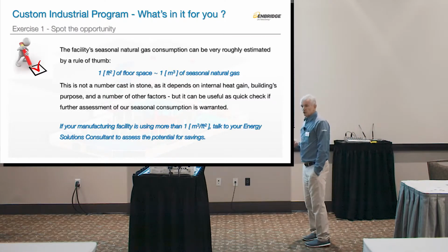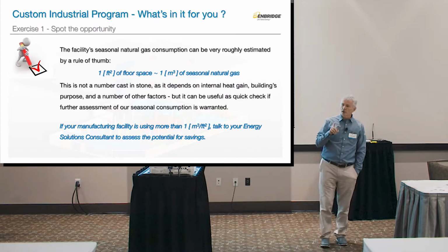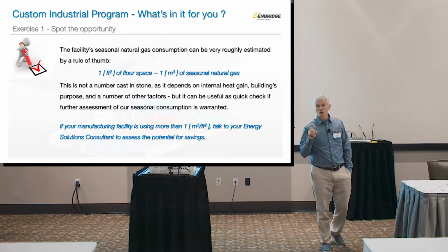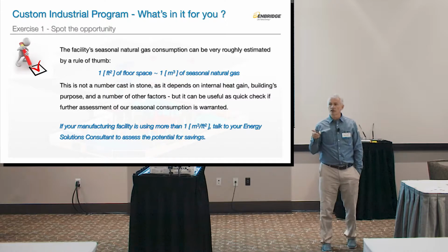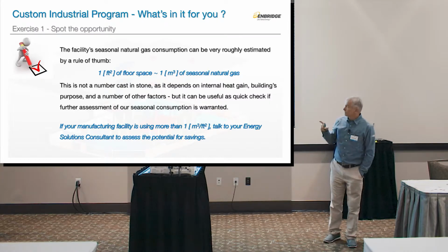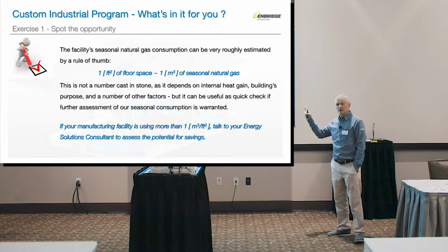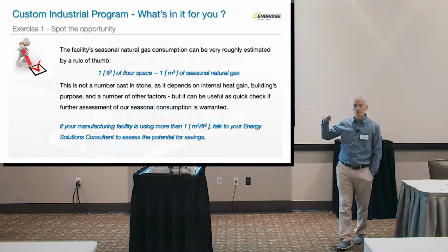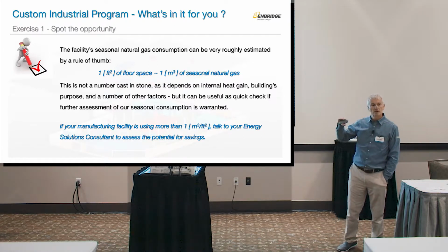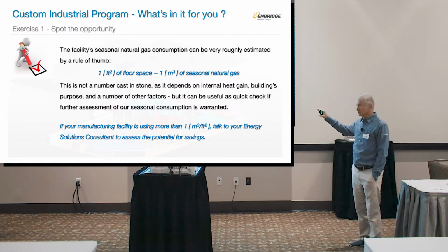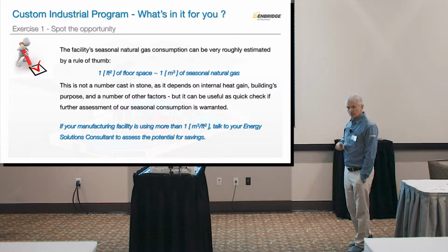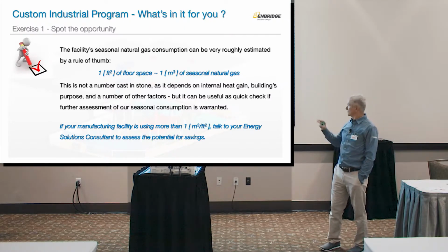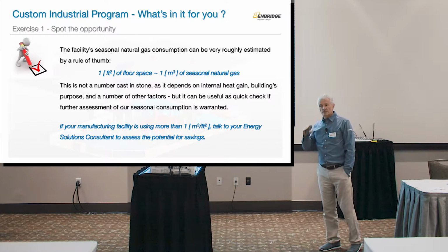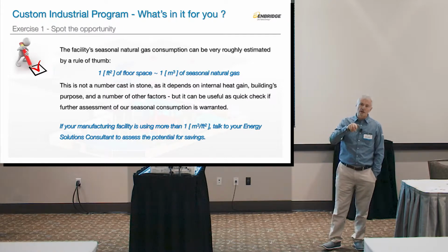As a rule of thumb, for 1 square foot of floor space, it should take you 1 cubic meter per year of heating. In industrial manufacturing facilities, actually lower than that. It's probably around half that. But even in a warehouse space, this is the rule of thumb that I usually look at, and if the number is above 1, I go and investigate why that is.